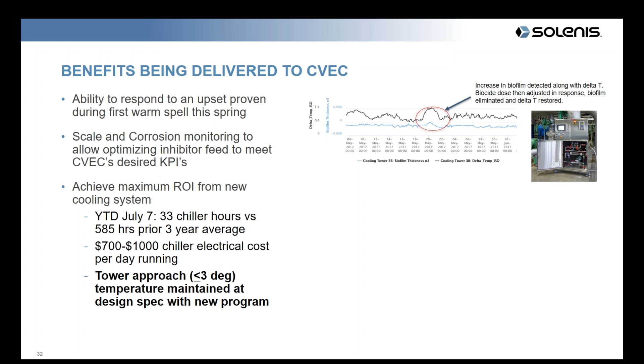So we're on target for a significant reduction in chiller operating hours required. Much of that benefit is due to our new cooling tower, which was designed with excess capacity and a lower than typical approach. The 3 degree Fahrenheit noted at the bottom of the slide isn't typical in the industry—somewhere in the range of 8 to 10 degree approach might be more common. But the clear point systems give us assurance that we're able to sustain that performance long term, and we haven't seen any deficiency or slip in that approach.